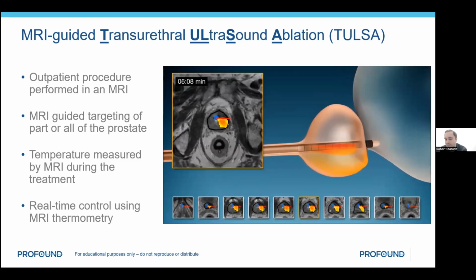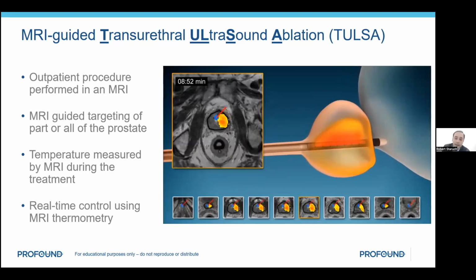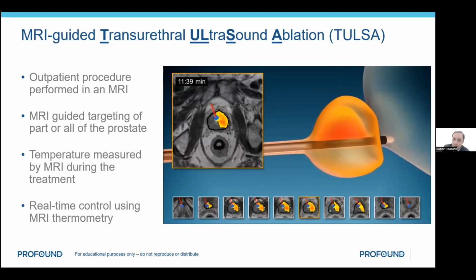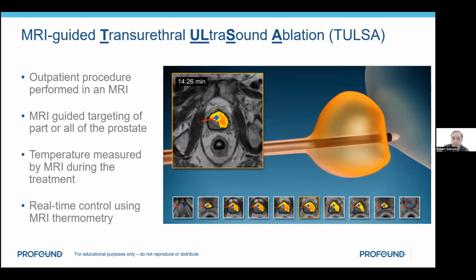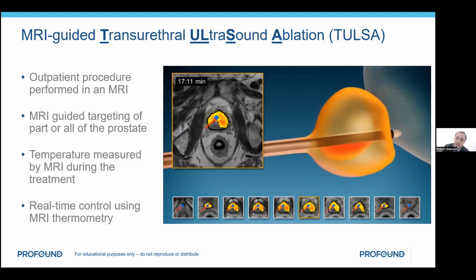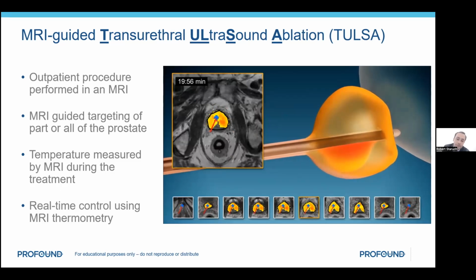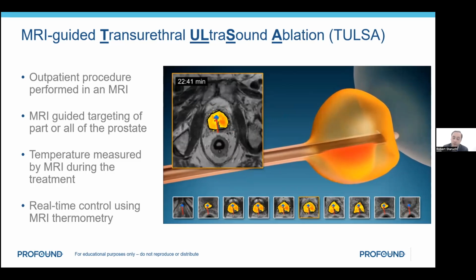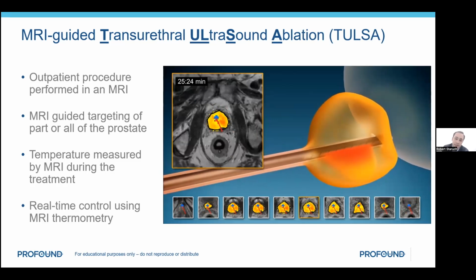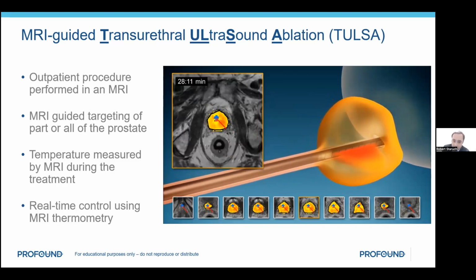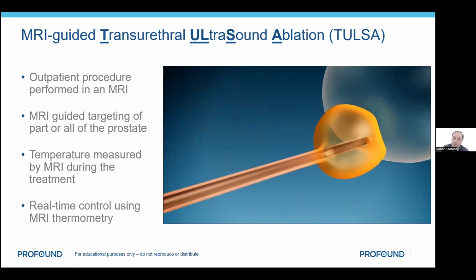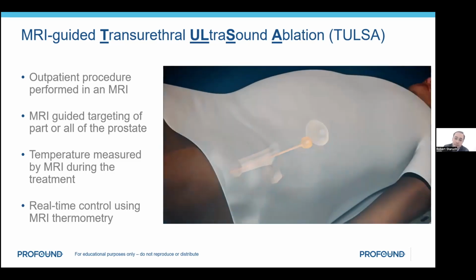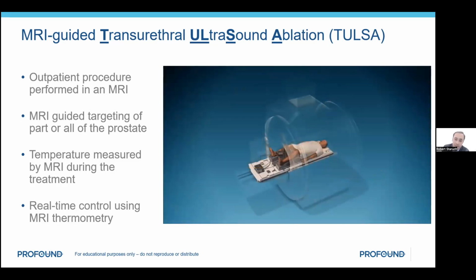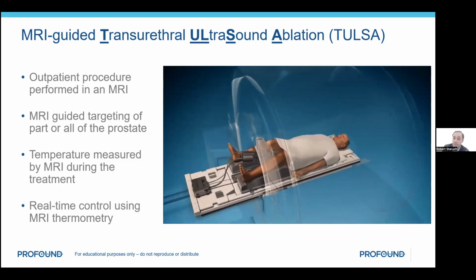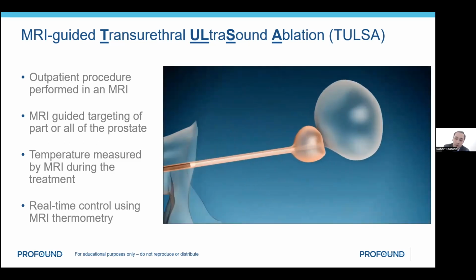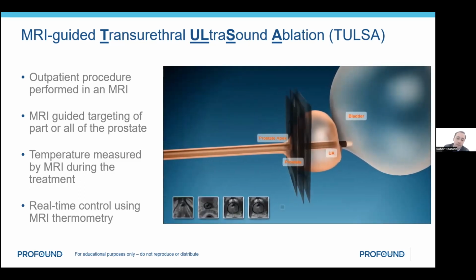And they can choose to ablate a small sector of the gland, or in this case, it's really the entire prostate. And then you can see these color overlays, which are displayed during the ablative procedure. And those color overlays are related to the temperature in the prostate, which is measured quantitatively. Every 5 seconds during the treatment, there's a volume of images that spans from beyond the apex to beyond the base of the gland, and a fairly wide field of view into the rest of the pelvis, which then with a resolution of 2 millimeters by 2 millimeters shows the actual temperature in every spot of the prostate and the surrounding tissues, which the physician can then use to make changes to their ablation plan, or to decide to pause and abort the treatment if necessary.